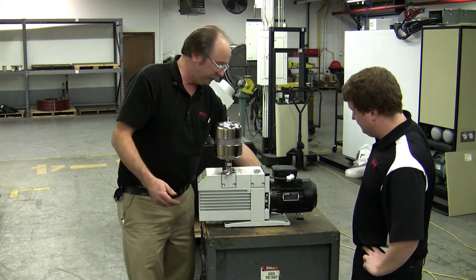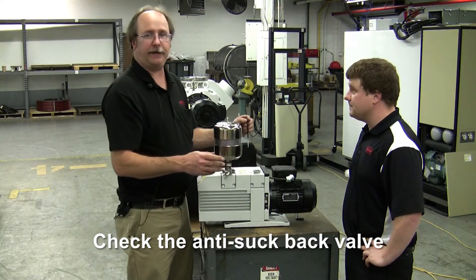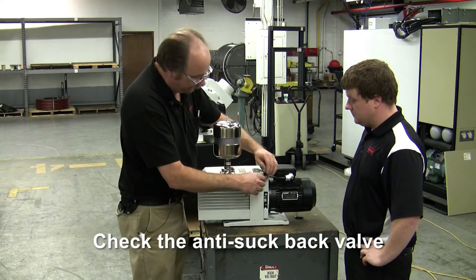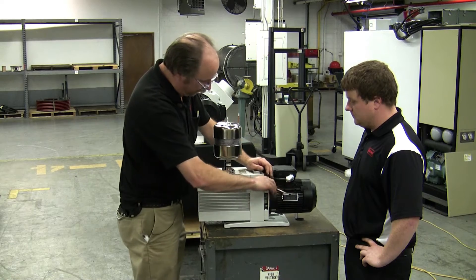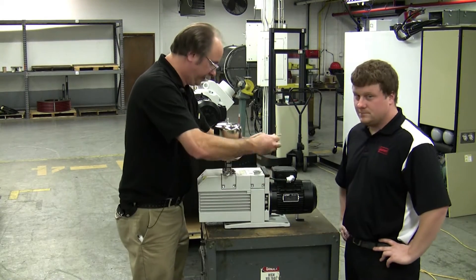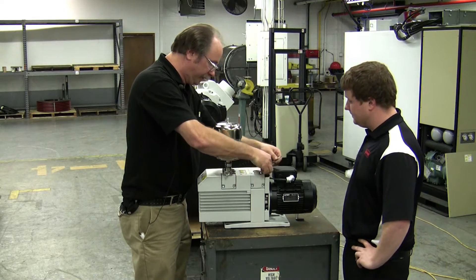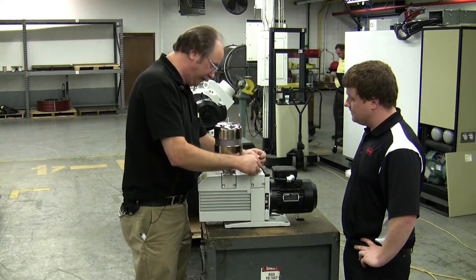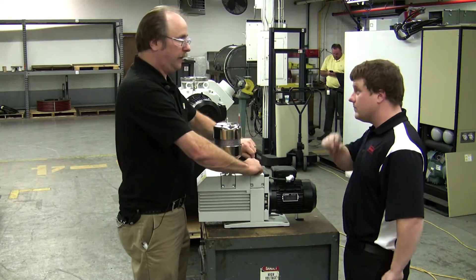The next thing I would recommend doing is inspecting the anti-suckback valve, and this is fairly easily done. We've removed the inlet — there are four screws here on top. This is the inlet flange. It's important to note that this inlet flange can be mounted in a vertical position, as you see here, and it can also be mounted horizontally.